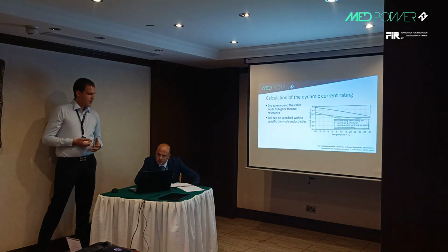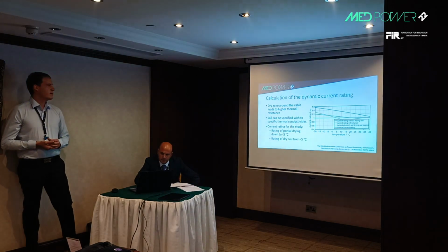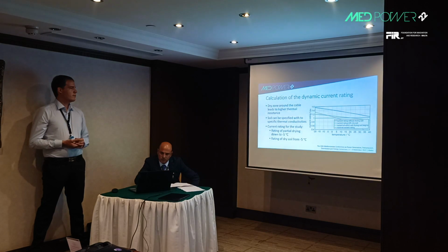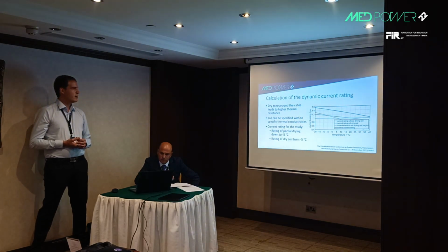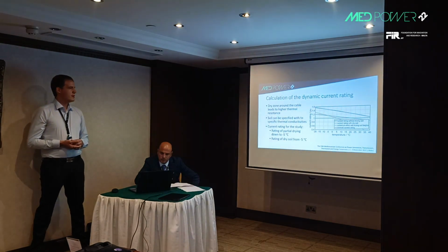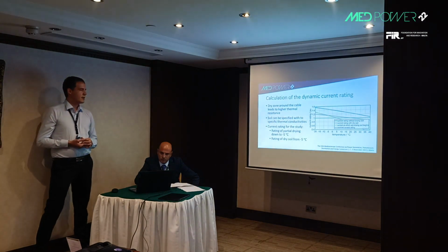begins. And for my study, we use the current rating from the orange line down to -5 degrees, and then the green line from -5 to the end. And at 20 degrees, the current rating is under the nominal current rating.